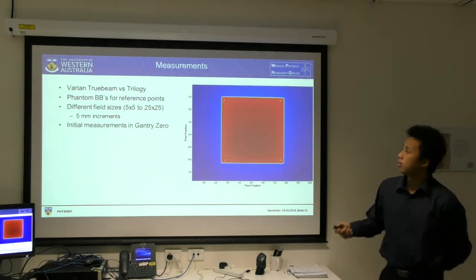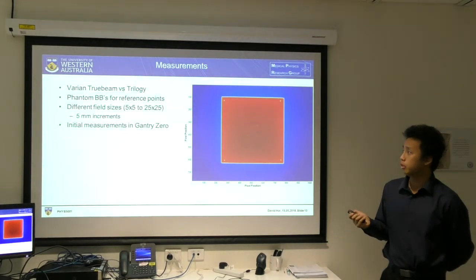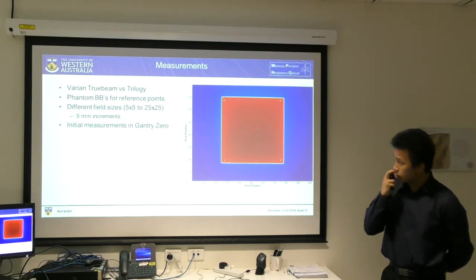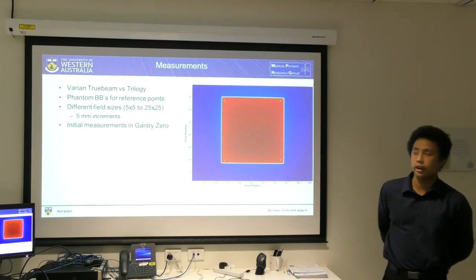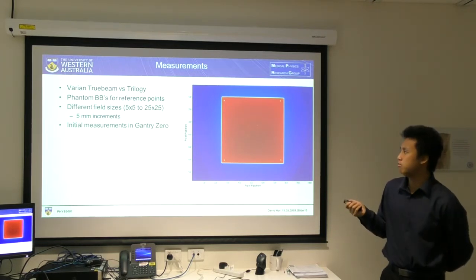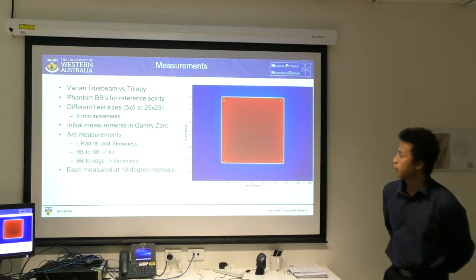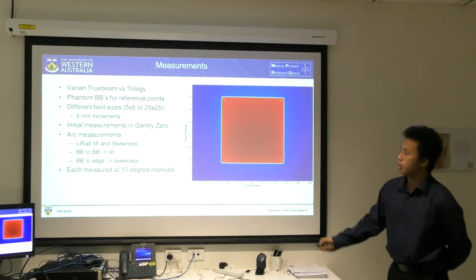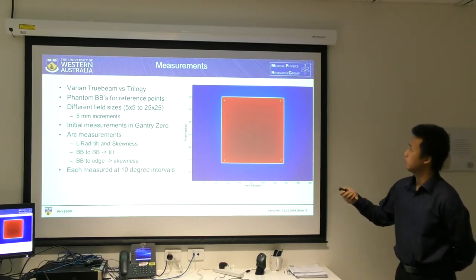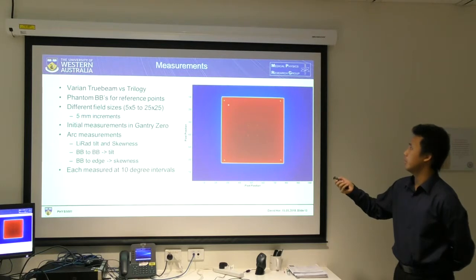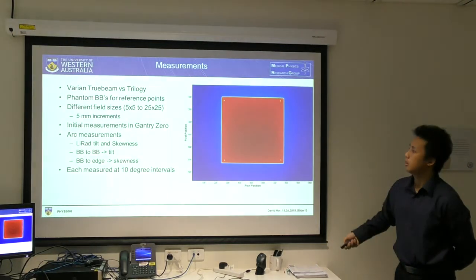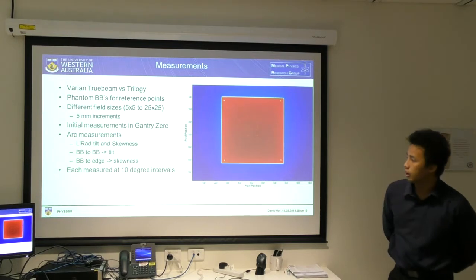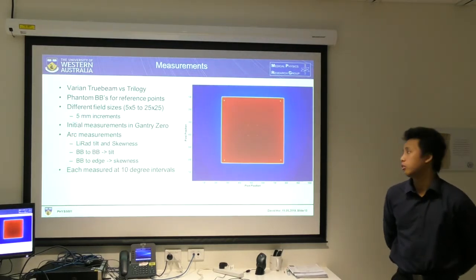For the measurements, I'll be comparing between the Varian TrueBeam versus Trilogy. The ball bearings in the phantom serve as reference points so I can measure distances. For initial measurements at Gantry Zero I'll have about five different sized fields from 5x5 to 25x25. During arc measurements I'll also include the tilt and skewness of the light radiation field — the ball bearings measure tilt by the distance difference between them, and skewness is measured from the BBs to the edge. All these are measured at each 10 degree interval in the 360 degree rotation.